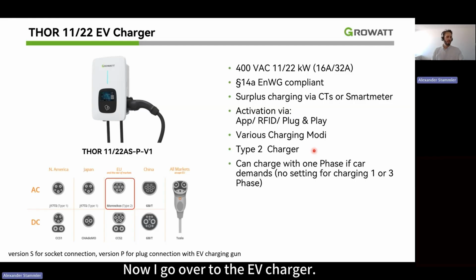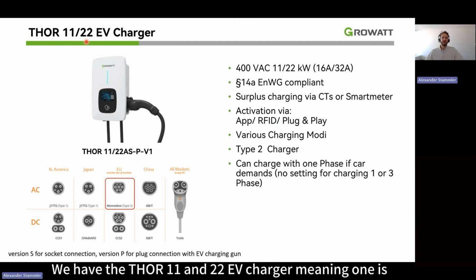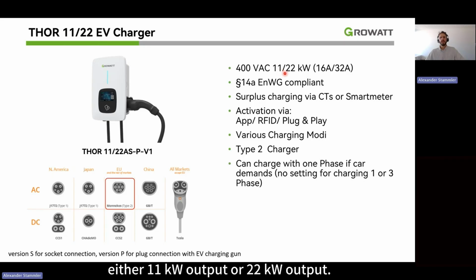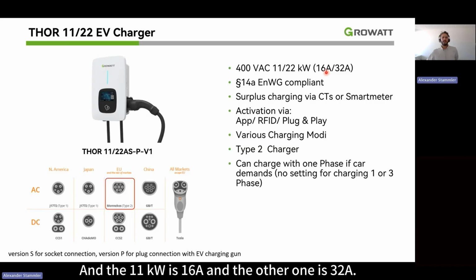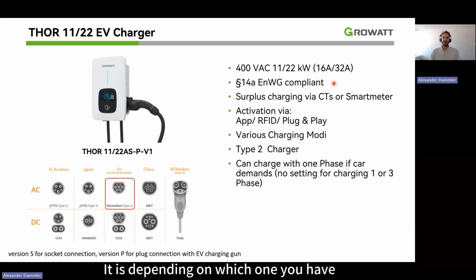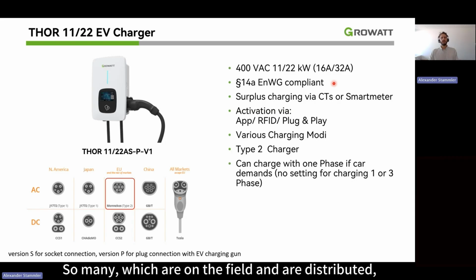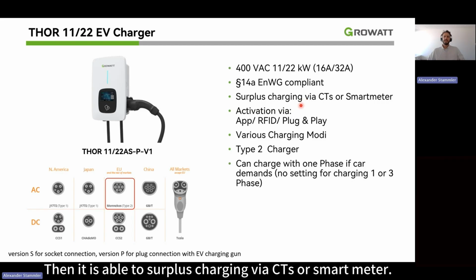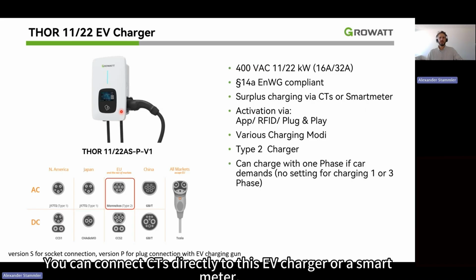Now I go over to the EV charger. We have the Thor 11 and 22 EV chargers, meaning one is either 11 kilowatt output or 22 kilowatt output. It uses 400 volt AC, so it's a 3-phase system, of course. The 11K is 16 ampere and the other one is 32 ampere. Depending on which one you have, it is compliant with paragraph 14A, which I will show later on, but you need a certain sticker on the EV charger. Many which are in the field and distributed do not have the sticker, but I will show you later. Then it is able to do surplus charging via CTs or smart meter. You can connect CTs directly to this EV charger or a smart meter.